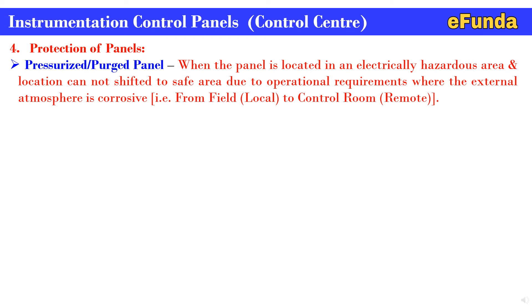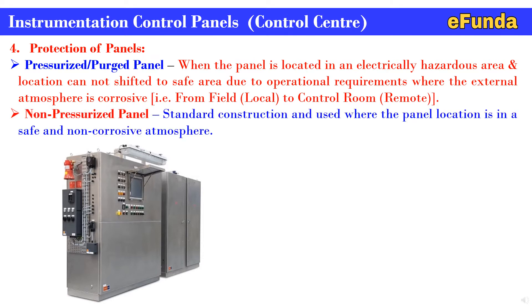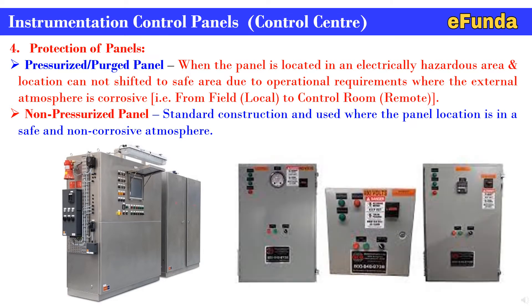Protection of panel: first, pressurized panel — when the panel is located in an electrically hazardous area and the location cannot be shifted to a safe area due to operational requirements, or where the external atmosphere is corrosive. The photograph shows a purge panel which is an enclosed panel located in a hazardous area with related accessories and instruments mounted inside. Second, non-pressurized panel — standard construction used where the panel location is in a safe area and a non-corrosive atmosphere. The photograph shows normal panels used for installation of various instruments and indicating devices.